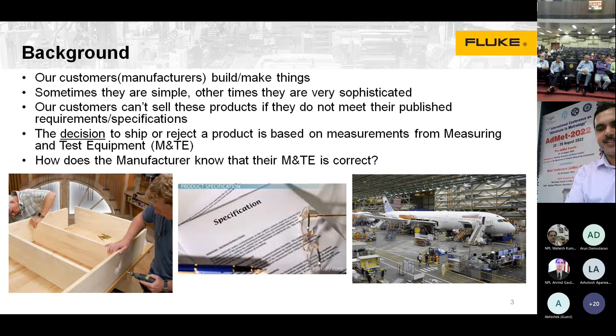As a background, our customers, the manufacturers, build and make many things. Sometimes they are simple, other times they are very sophisticated. Our customers can't sell these products if they don't meet their published requirement specifications. So the decision to ship or reject a product is based on measurements from measuring and test equipment, or M&TE in short. How does a manufacturer know that their measurement and test equipment is correct? They need to get it calibrated and tested by the NMIs or labs accredited to 17025.